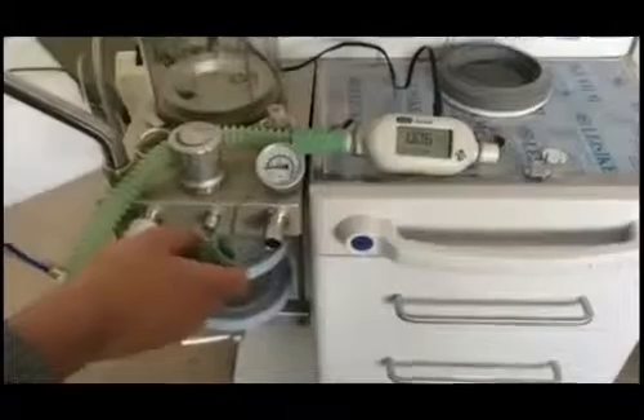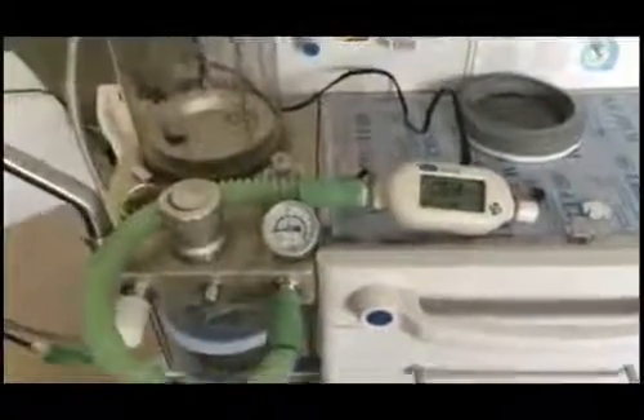Now we will connect the flow meter to the expiration port. Now we will connect the flow meter to the inspiration port. After connecting the flow meter, now we will set the electronic flow meters to 0. Please set all the electronic flow meters to 0. The next step is to press the start key. The first calibration is the calibration of the 0.